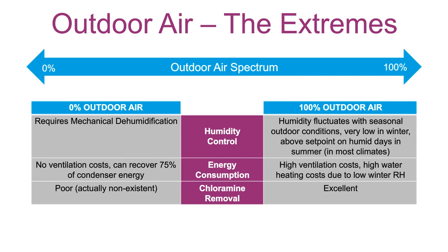And well, if you have 0% outside air, then you obviously need mechanical dehumidification or some form of other dehumidification because you have nothing happening from outside air. You would have no ventilation costs in that regard because you have no load. So you could recover a lot of the energy you use for dehumidification and heat cool water and heat air with it because you don't have any ventilation costs there. So it'd be a very good energy efficient machine, would do a very poor job, actually non-existent job of removing any chloramine from the space.